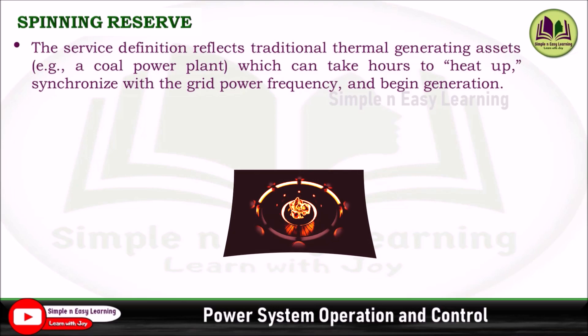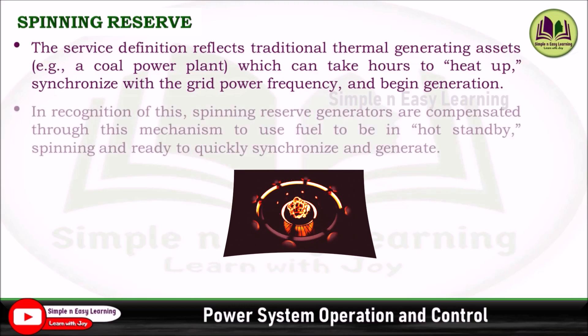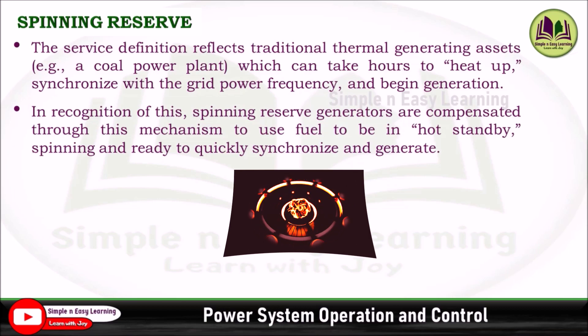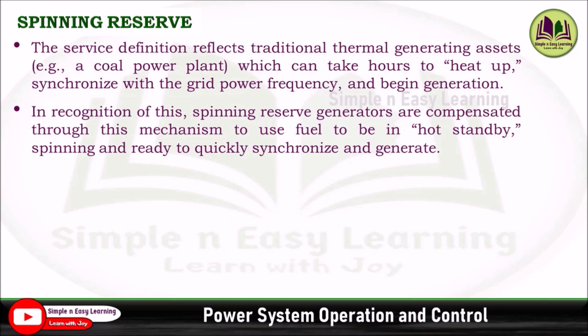The service definition reflects traditional thermal generating assets. For example, a coal power plant which can take hours to heat up, synchronize with the grid power frequency, and begin generation. In recognition of this, spinning reserve generators are compensated through this mechanism to use fuel to be in hot standby, spinning and ready to quickly synchronize and generate.